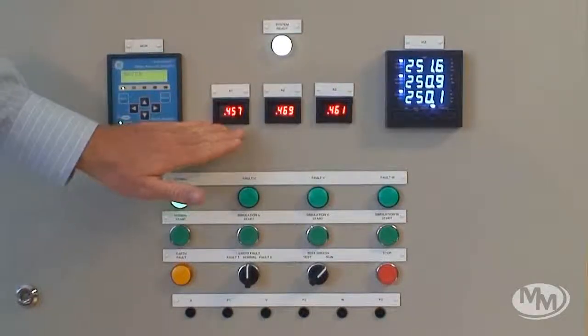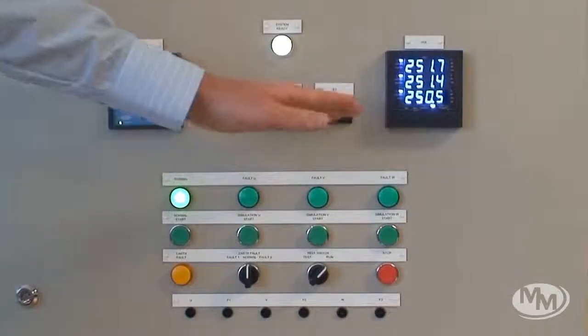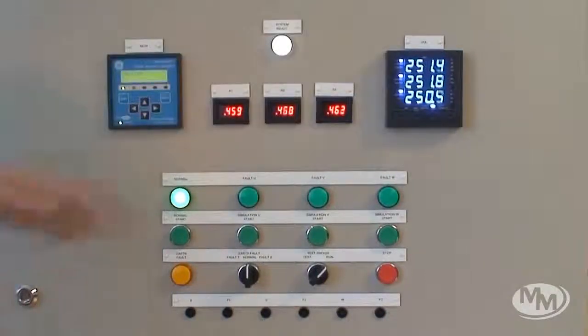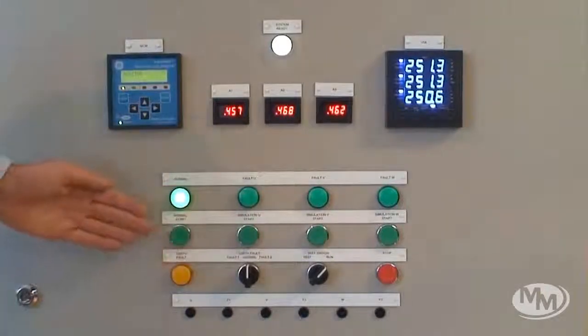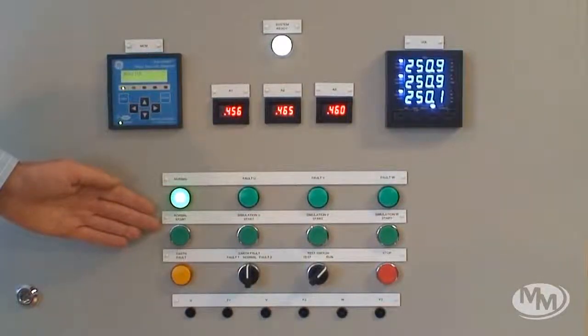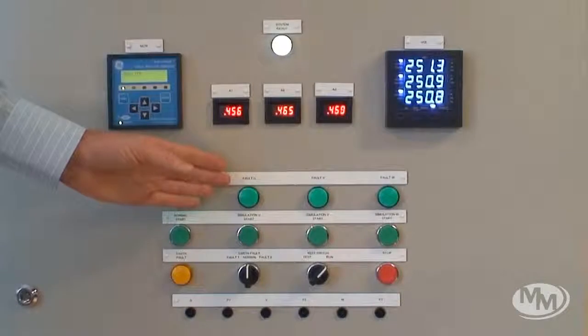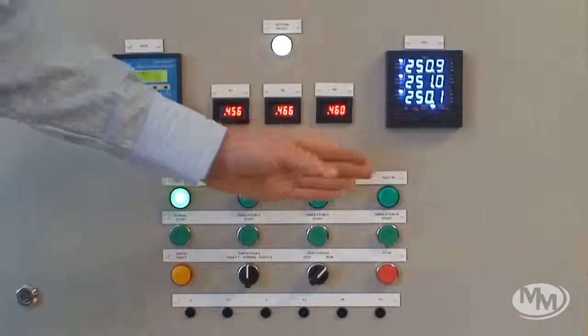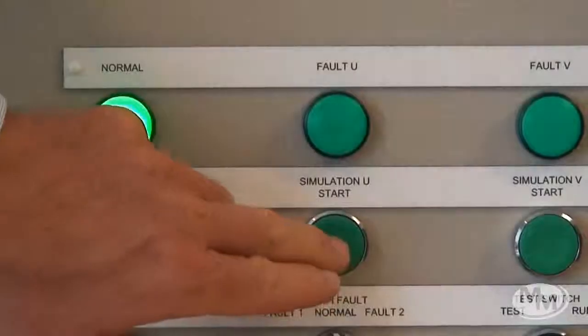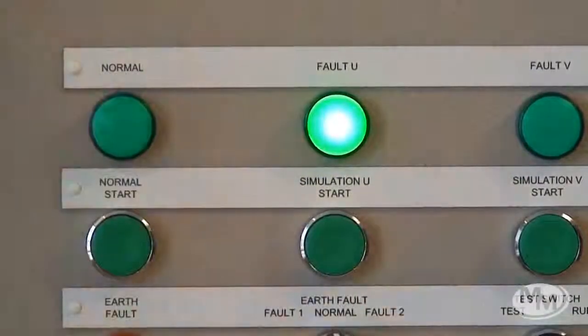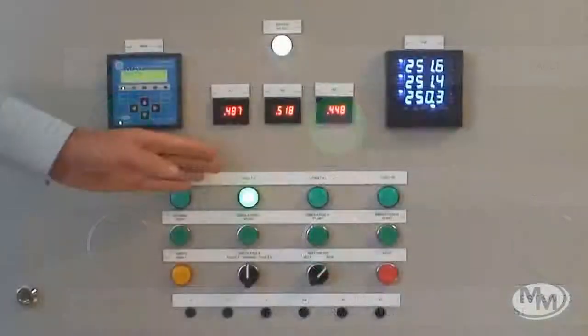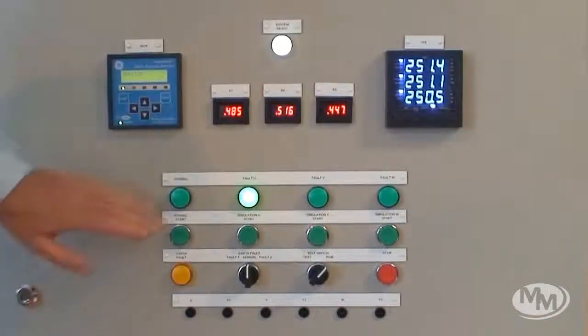We can see here there is current per phase and also phase voltages. Along here are the push buttons for introducing electrical faults. We can introduce a turn fault on either U, V or W phase simply by pushing the simulation start button on the corresponding phase. Resetting is as simple as pushing the normal start push button.